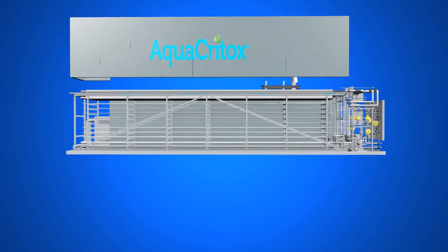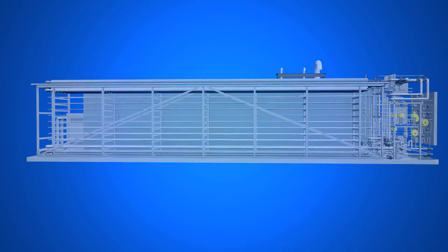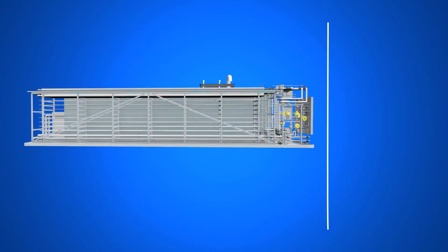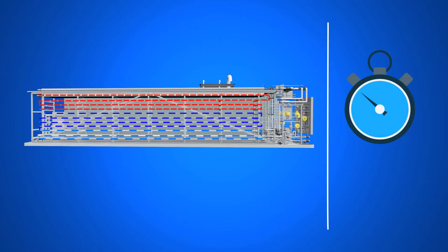Increased operating pressure and the use of oxygen as oxidant leads to up to 1200% increase in oxygen transfer rate, which can in other systems be a rate limiting factor. Increased reaction temperature also increases reaction rate and the number of compounds that can be oxidized. Combining all these factors have allowed us to significantly reduce retention times to just over 10 minutes.